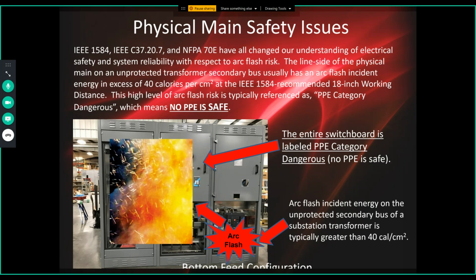And that is absolutely a flawed methodology, because if the arc flash takes place on the line side of the breaker, it will absolutely propagate through the switchboard. Just as in shock hazard events, electricity follows all paths, but favors low impedance paths. And in an arc flash event, the rapidly expanding pressure and plasma wave favors low air pressure paths. And the low air pressure path is first inside that switchboard itself and through openings and vents and seams.